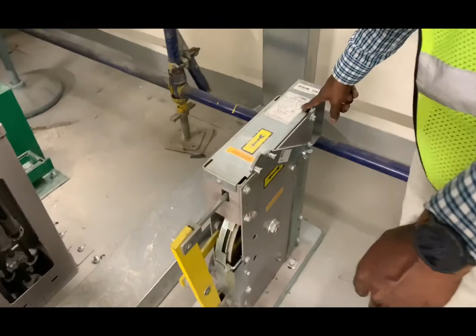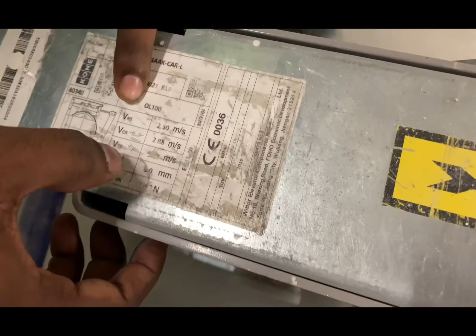There is saying 3.5, right? If it goes to 3.5, the OSG will be engaged. If you see here, this is the 2.5 meter. This is the rated speed, 2.5 meter per second. If the speed goes to 2.88, it will trip.